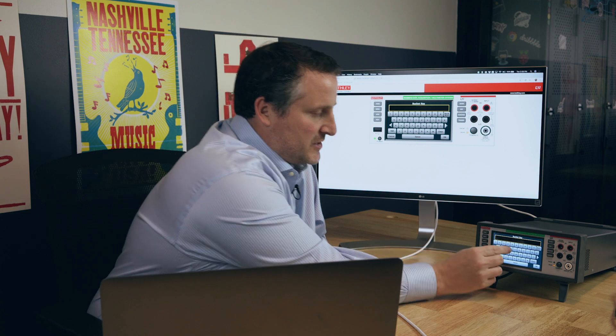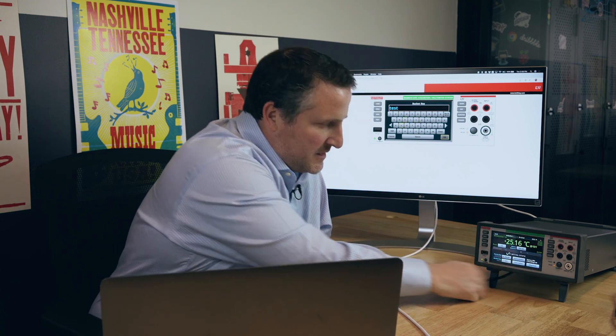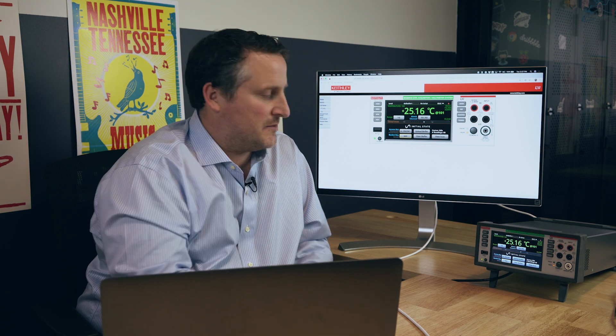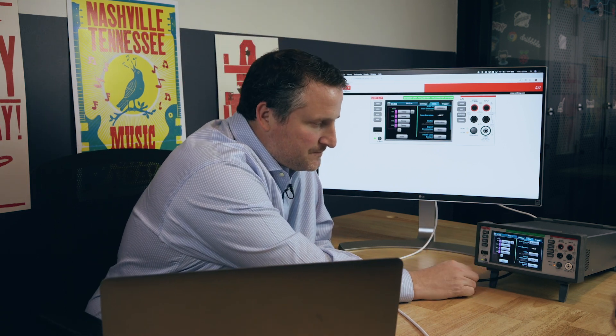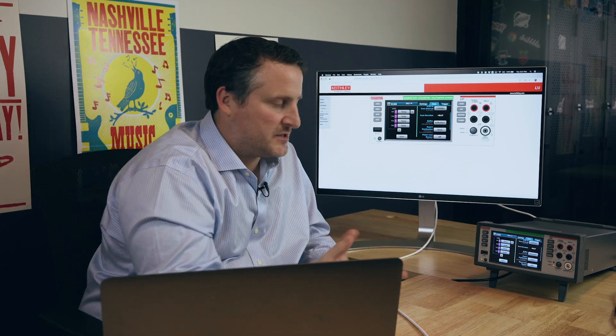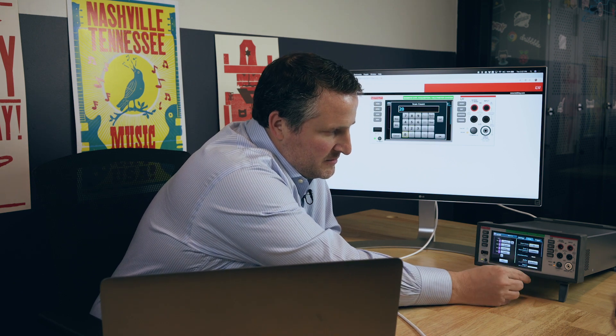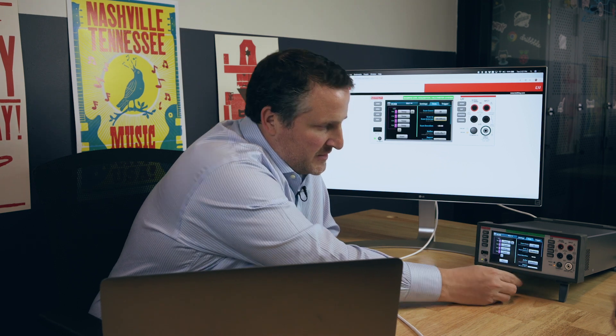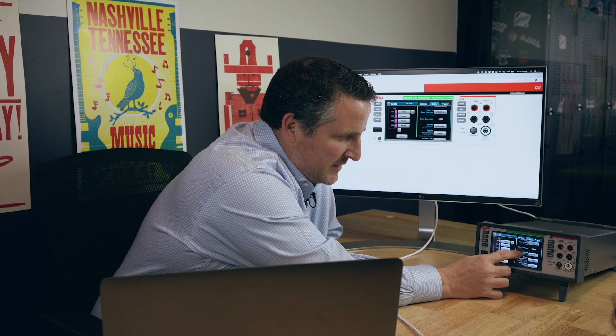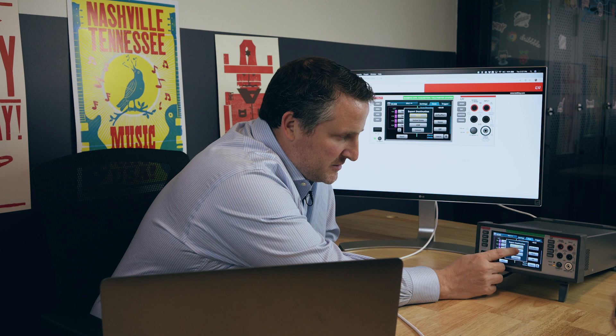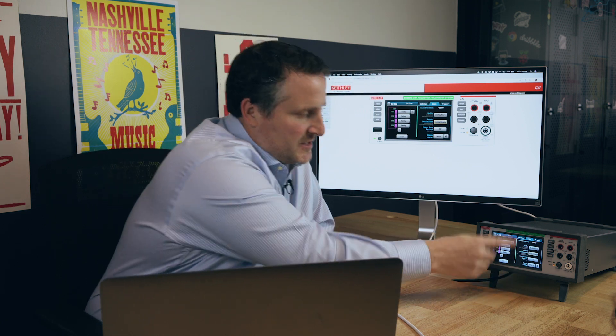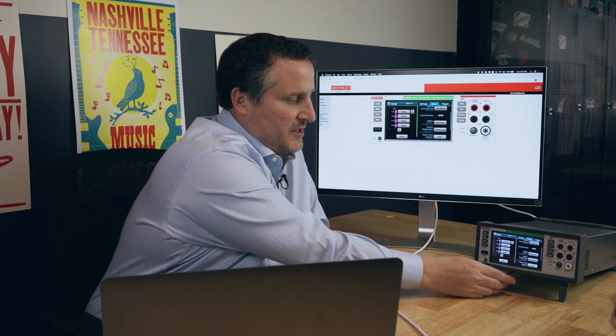The next thing is to name this data — it's called the bucket key for Initial State. I'm going to name it 'Test' and say OK. Now everything is set up and ready to take a measurement. I've got four temperature channels. I'll go to the Scan tab, set it to 20 samples at 0.5 seconds between them — about 10 seconds worth of samples. A key new option here is the export destination, where you can now select Initial State instead of a USB key. I'm going to set the export destination to Initial State and click Start.